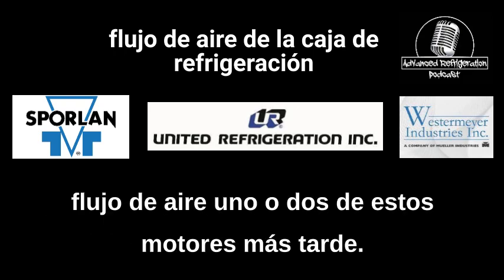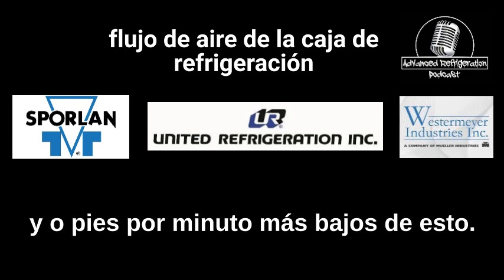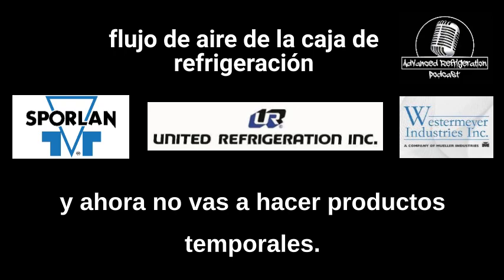One or two of these motors later, and now your case has 50 to 60 CFM, cubic feet per minute, lower out of this, and now you've changed the whole TD of the coil, and now you're not going to make product temps.